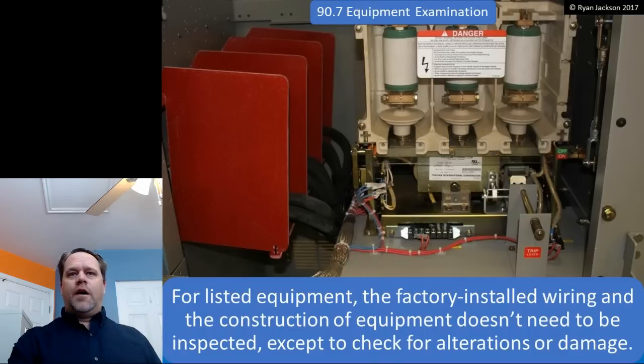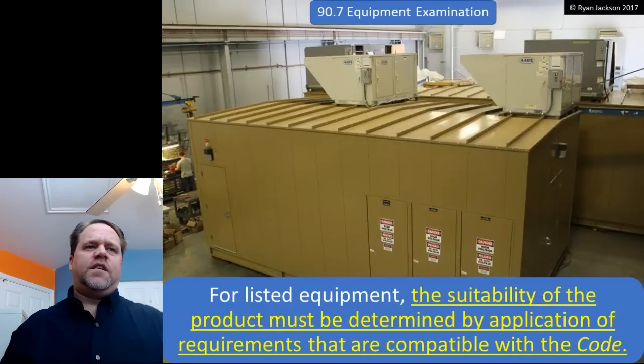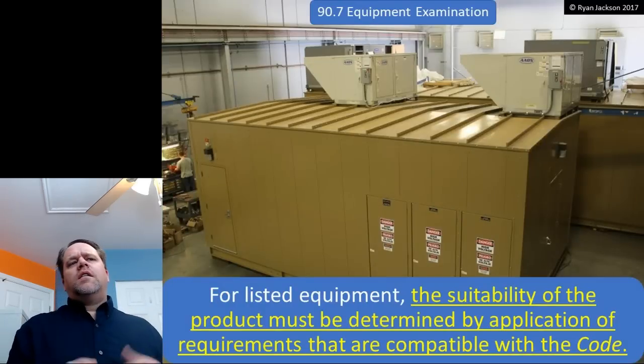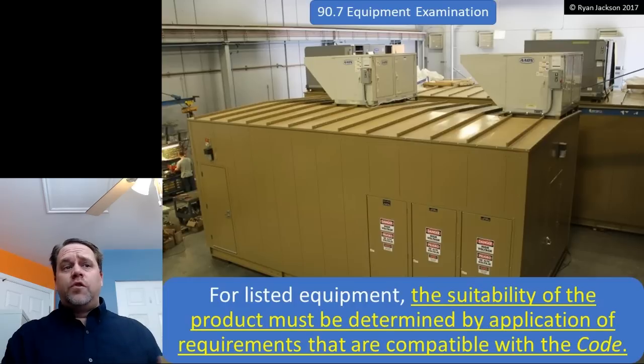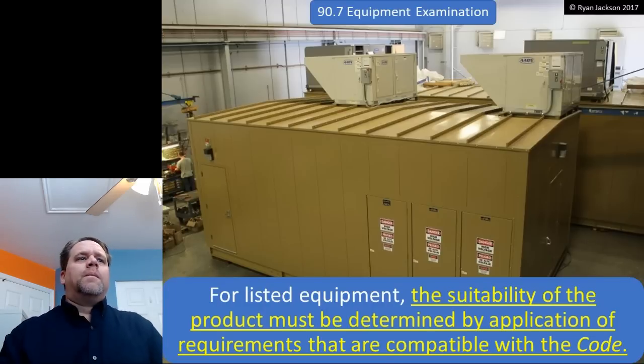So there you go. New to the 2017, and I'm paraphrasing here, it says for listed equipment, suitability of the product must be determined by applying requirements that are compatible with the code. So in other words, the fact that your equipment is listed doesn't negate code compliance. It still has to comply with the code even though it's listed.